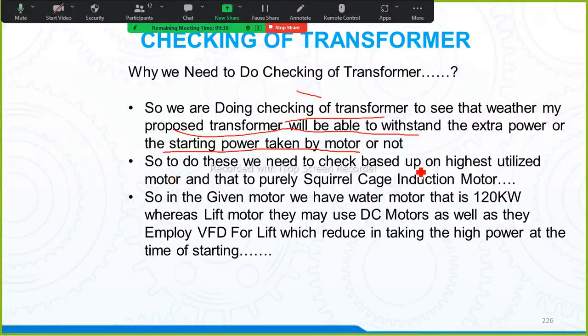So to do this, we need to check based upon the highest utilized motor, and that too a purely squirrel cage induction motor. In the given motors, such a motor is your water motor, which is given as 120 kilowatt. Whereas the lift motor uses a DC motor as well as a VFD, variable frequency drive, per lift, which reduces the high power taken at the time of starting. So the mostly used motor is your water motor. Now let us check whether my transformer will be able to withstand the high starting current taken by the motor or not. That is your water motor, which is 120 kilowatt.